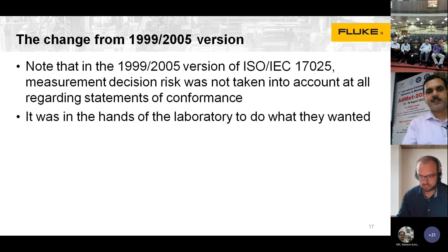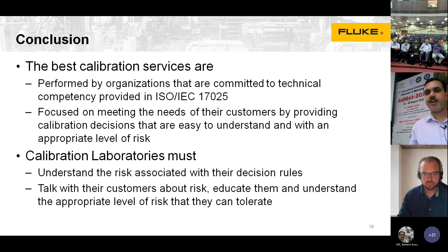Now, to conclude, the best calibration services are performed by organizations that are committed to technical competence as per ISO/IEC 17025, for calibration and testing services. These services are focused on meeting the needs of their customers by providing calibration decisions that are easy to understand and with an appropriate level of risk. Calibration laboratories must understand the risk associated with their decision rules, and they need to talk with their customers about risk, educate them, and understand the appropriate level of risk that they can tolerate.